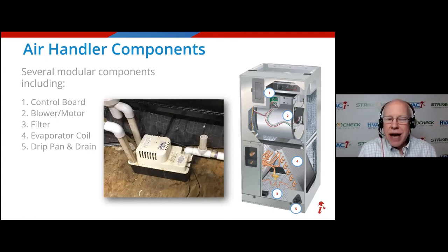So not all systems have this, but if they do, you know what it's doing. The condensate's going in there. You're pumping it to a drain or somewhere outside. Those fail all the time as well. So then they can be part of the water loss too. So again, not all systems have those, but many do.